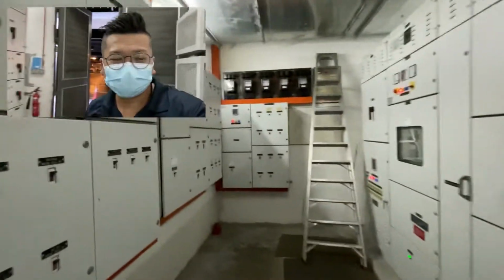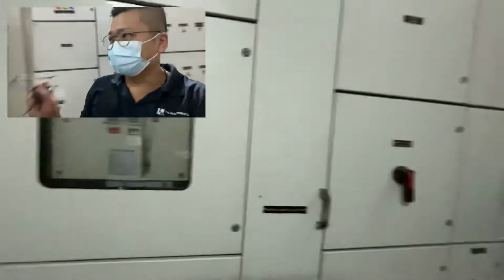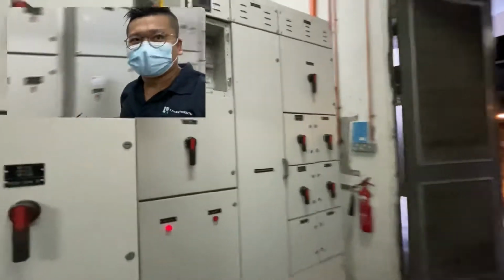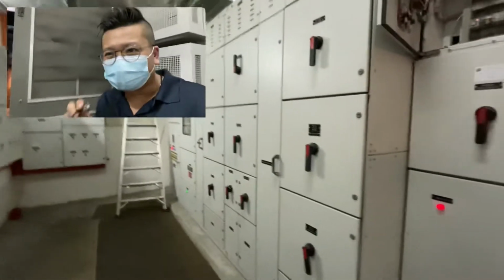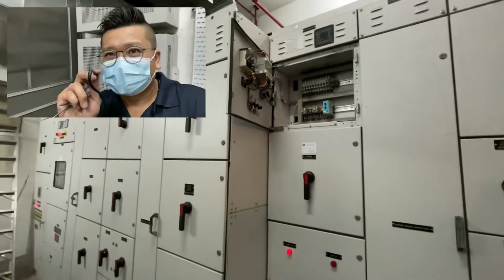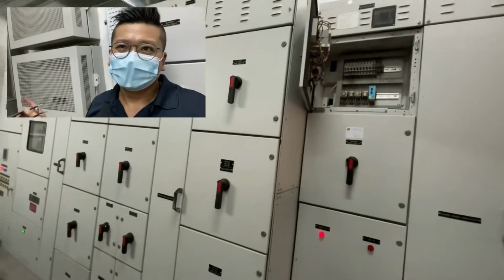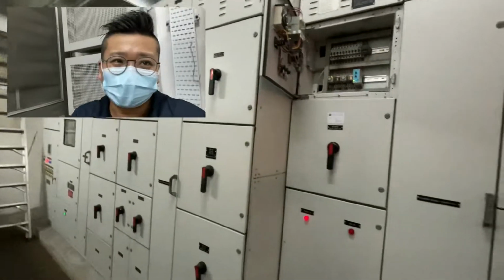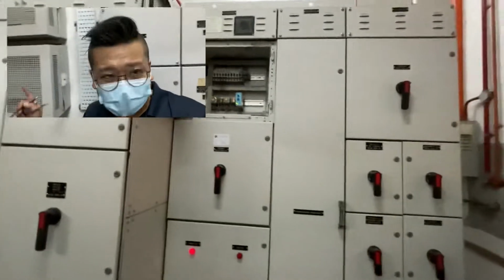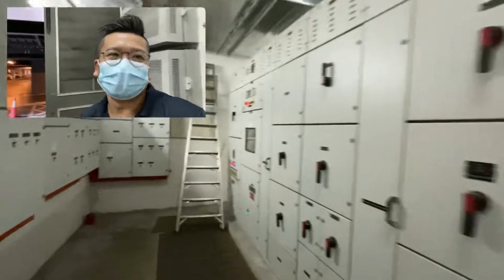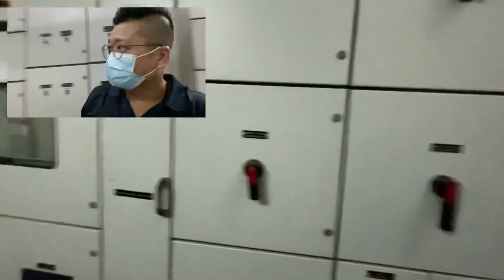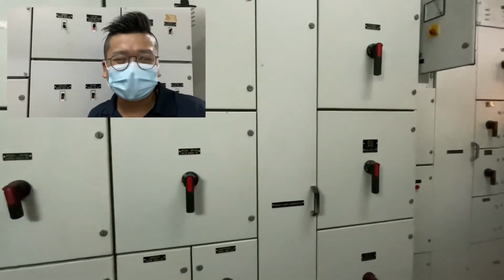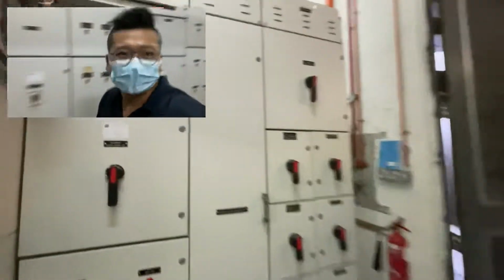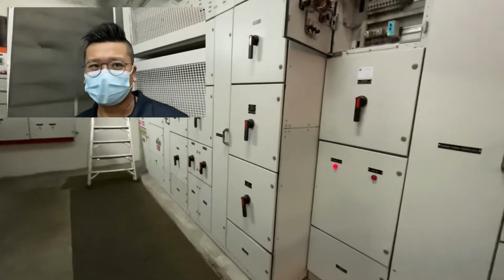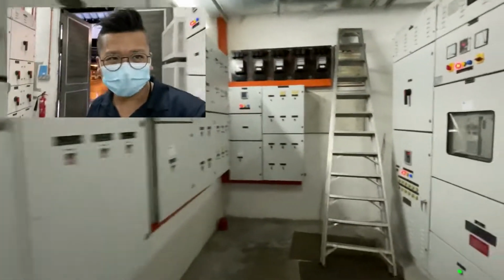Okay, by using this way, I can confirm that when there's a TNB power interruption or power supply interruption from the main source, the UVR relay here will call the genset to run. The same contact as I simulated just then can also call the genset to run. As I use this test to confirm, the panel here successfully called the genset to run and to turn off, so I'm pretty much confirmed the genset can automatically function properly during power interruption and during power normalization. Okay, the genset will stop automatically after 3 to 4 minutes. Then later we will have a visit to the genset room.